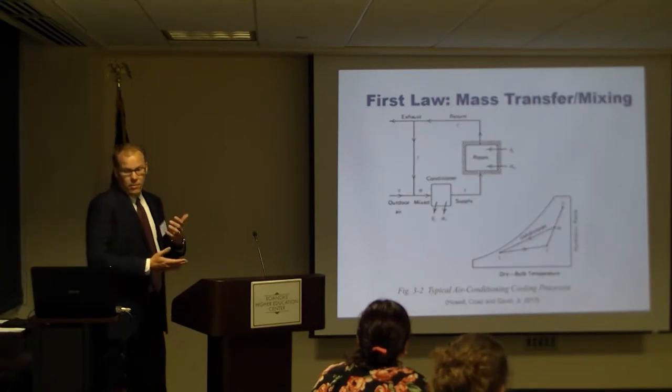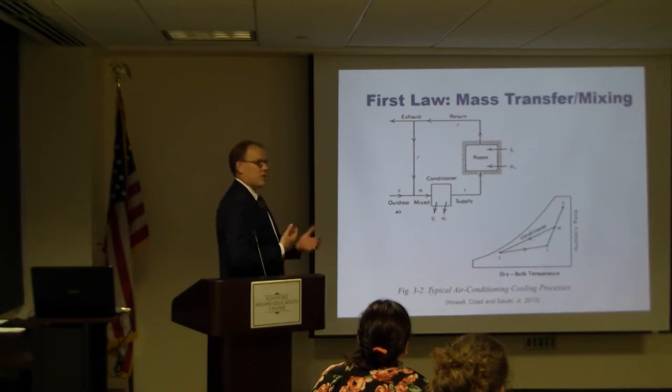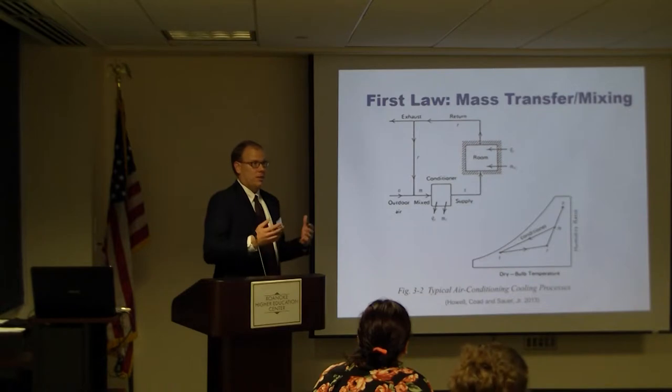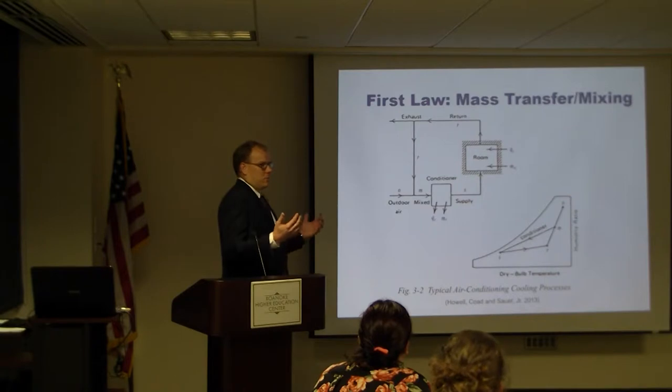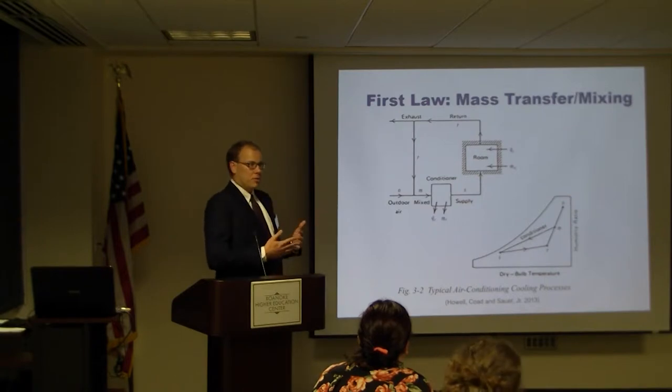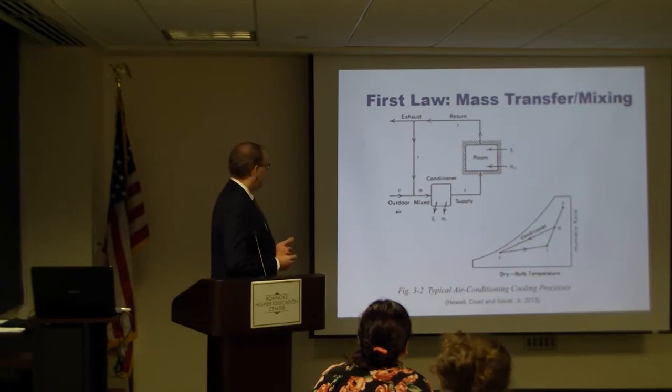How do we also have to look at mass transfer and mass mixing? We tend to mix airstreams. We have an airstream that comes back from the room, that's 78, 75, whatever temperature's in the room. We're going to mix it with outside air. That's going to have a different mass, a different temperature, a different humidity. So also we're doing equilibrium equations for what is the temperature that's going into our heat transfer device, adding heat to it or subtracting heat to it.